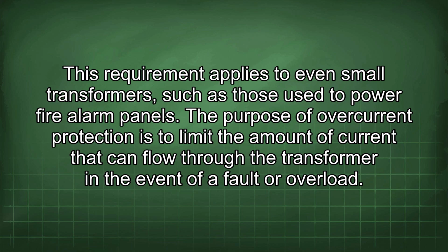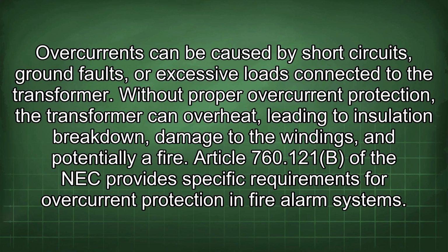The purpose of overcurrent protection is to limit the amount of current that can flow through the transformer in the event of a fault or overload. Overcurrents can be caused by short circuits, ground faults, or excessive loads connected to the transformer. Without proper overcurrent protection, the transformer can overheat, leading to insulation breakdown, damage to the windings, and potentially a fire.